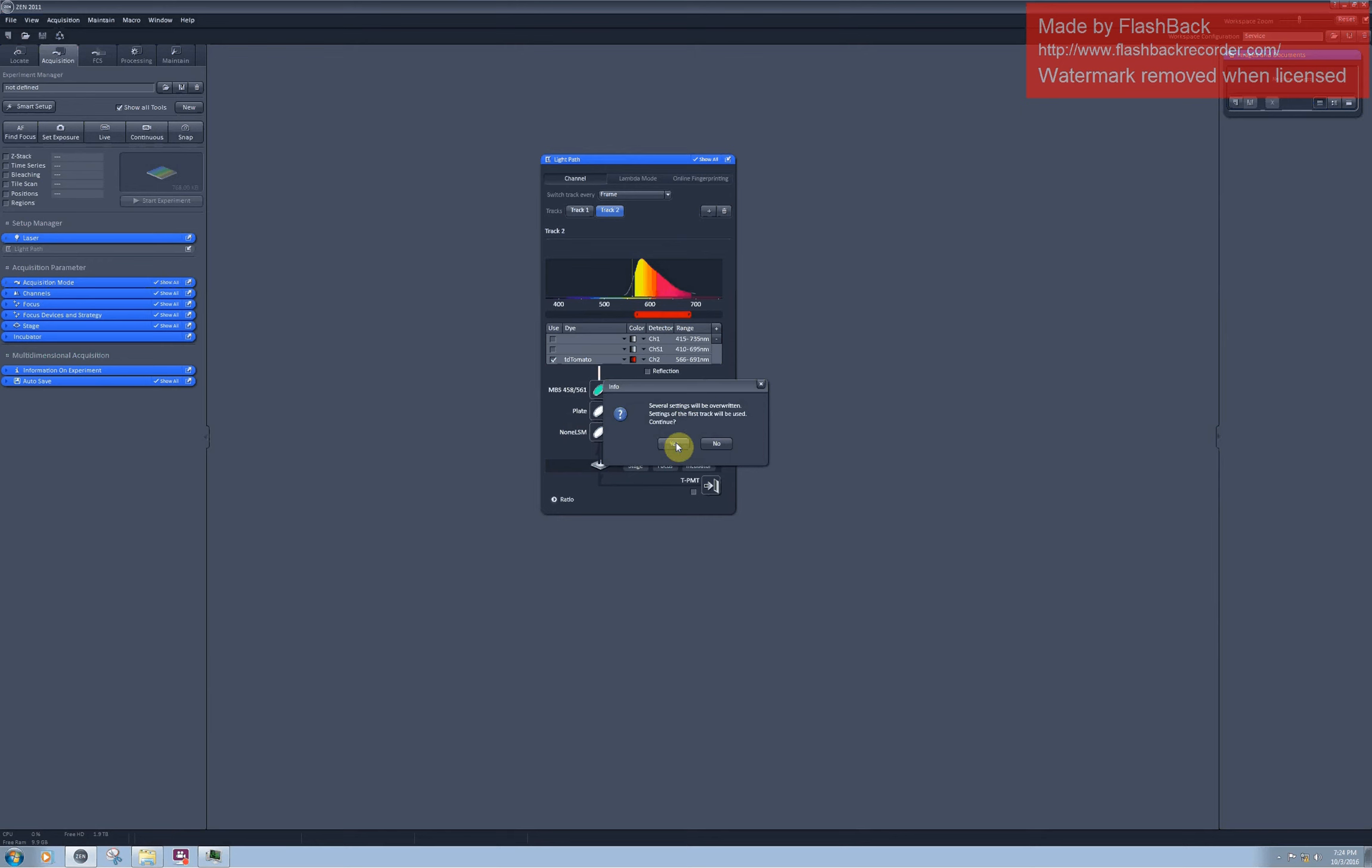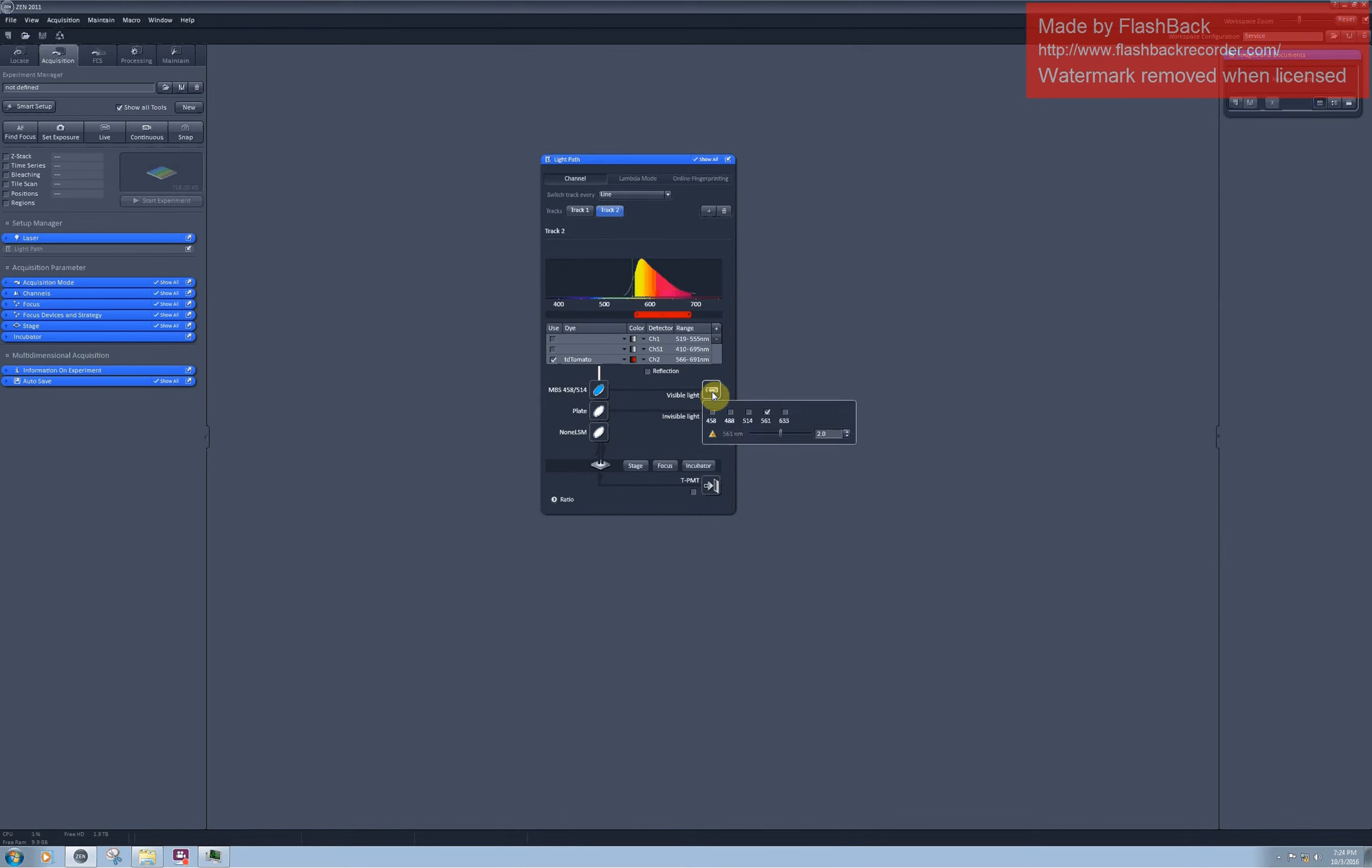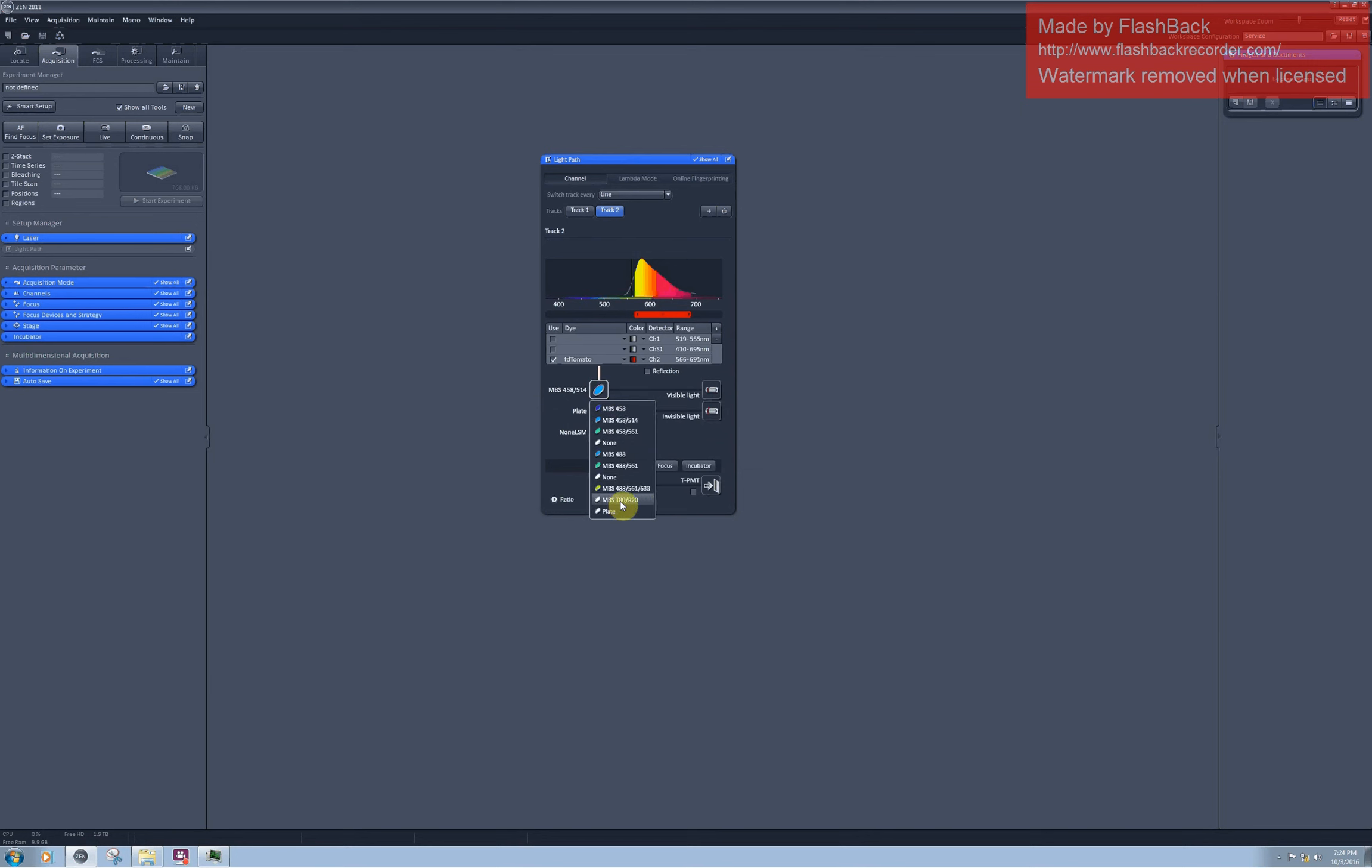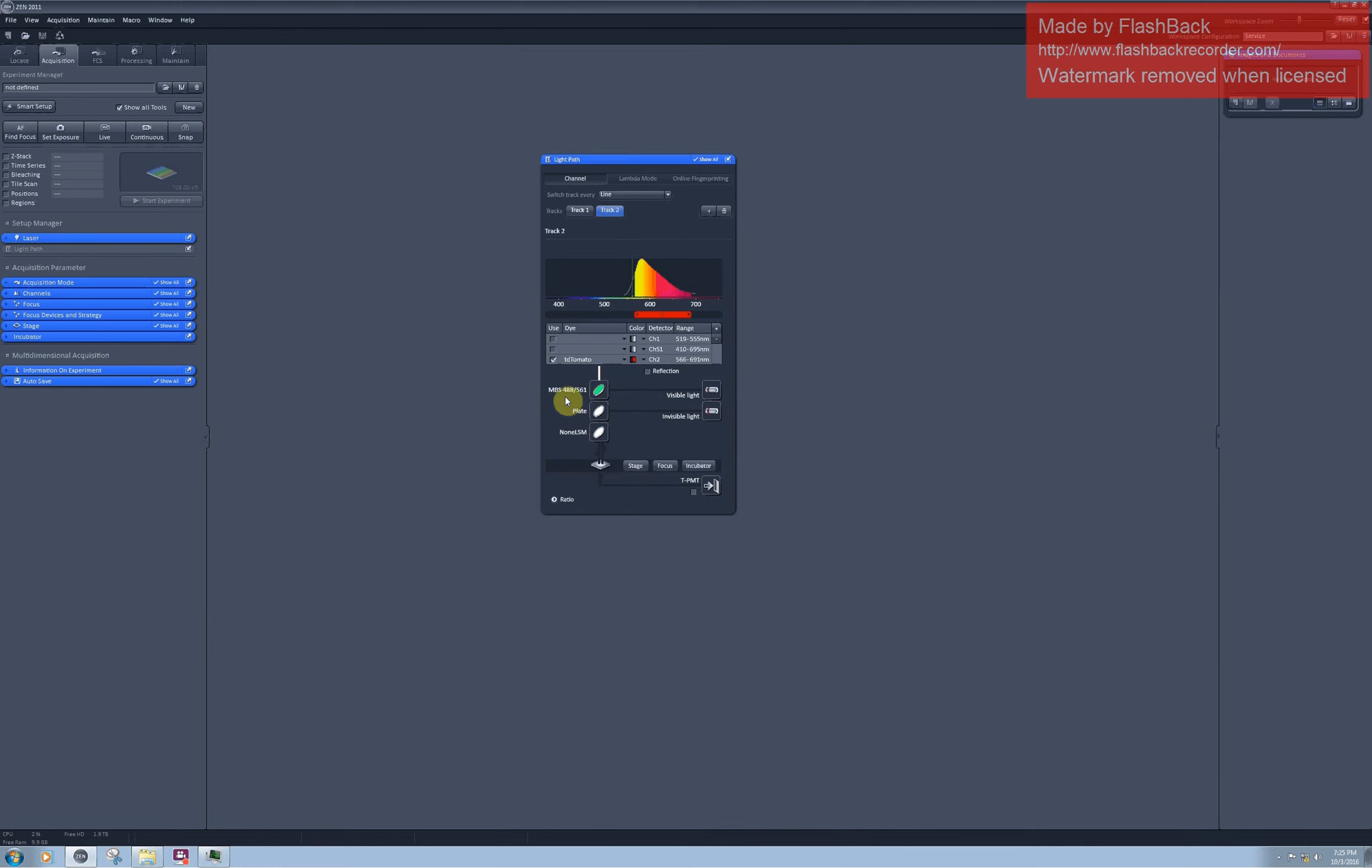If I click on yes here, you will see that now I have the same main beam splitter for track 1 and track 2. You can also see that this main beam splitter is not suitable for 561 nanometer laser. What I can do is change the MBS to this one, which transmits 80% of any light and reflects 20% of any light. This is apparently enough to have enough excitation on your sample and let enough emission from your sample to the detector. But I really don't like this solution. It makes things quite dim. So I would rather go with the main beam splitter 561 and switch every frame.